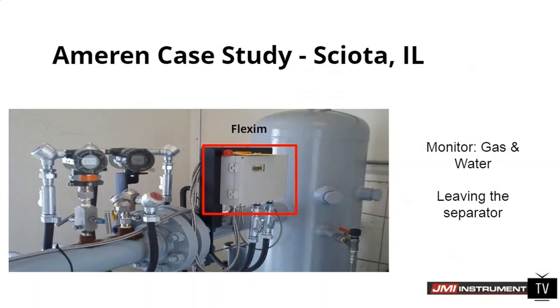And this is a common application. The transducers are actually down the pipe here a little bit, but this is a common application. In this case, we have another meter measuring the water leaving the separator, so they have to keep track of the amount of water they're putting back in the ground. They monitor the gas with this meter after the separator, and they monitor the water coming out of the separator after it's been separated.